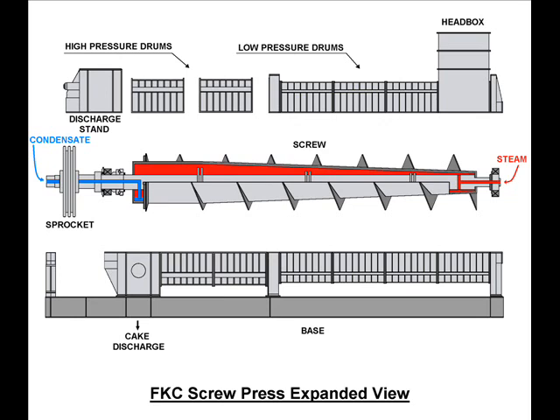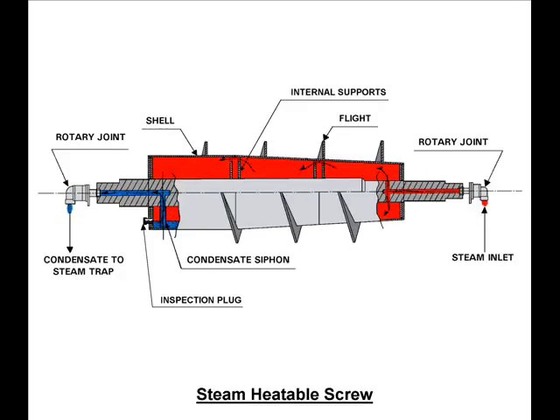The FKC screw press also has the ability to operate with steam. As illustrated, saturated steam enters the inlet end of the screw through a rotary joint. The steam travels a short distance through a passage in the screw shaft and then into the space between the screw shaft and the tapered screw shell. The steam does not come in contact with the sludge. Heat from the steam is transferred through the screw shell into the sludge.